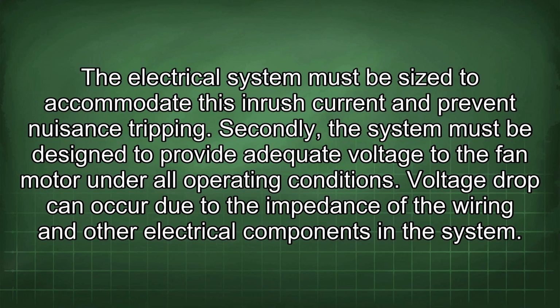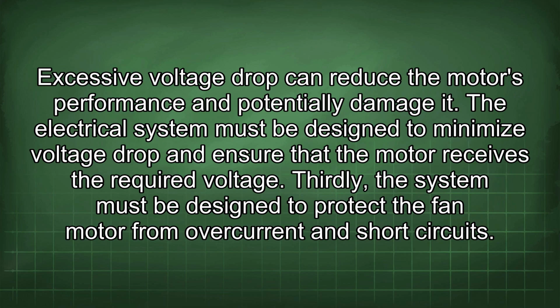Secondly, the system must be designed to provide adequate voltage to the fan motor under all operating conditions. Voltage drop can occur due to the impedance of the wiring and other electrical components in the system. Excessive voltage drop can reduce the motor's performance and potentially damage it. The electrical system must be designed to minimize voltage drop and ensure that the motor receives the required voltage.